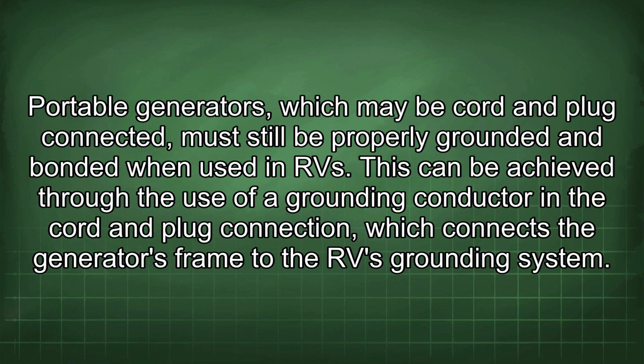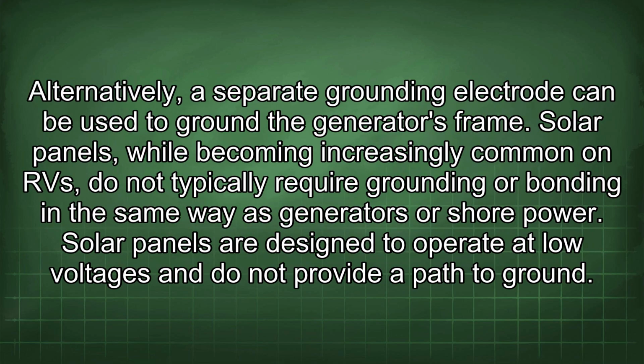Portable generators, which may be cord and plug connected, must still be properly grounded and bonded when used in RVs. This can be achieved through the use of a grounding conductor in the cord and plug connection, which connects the generator's frame to the RV grounding system. Alternatively, a separate grounding electrode can be used to ground the generator's frame.